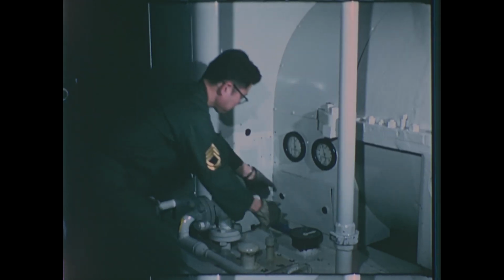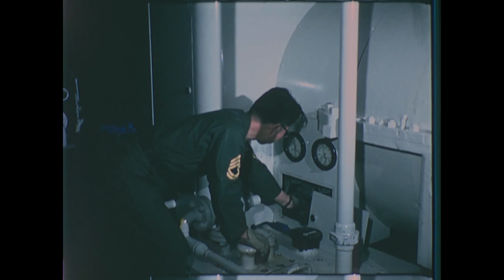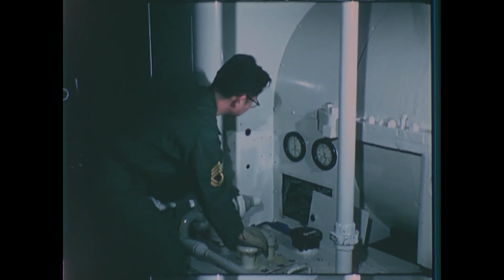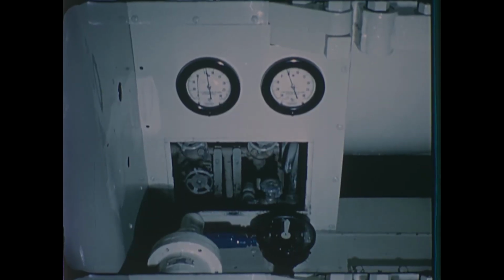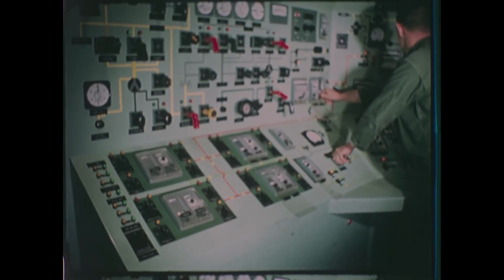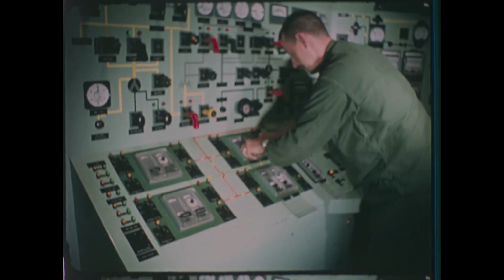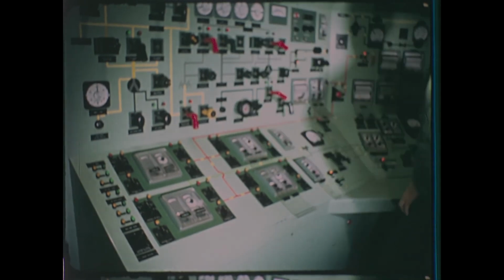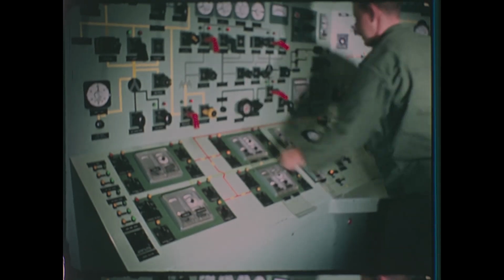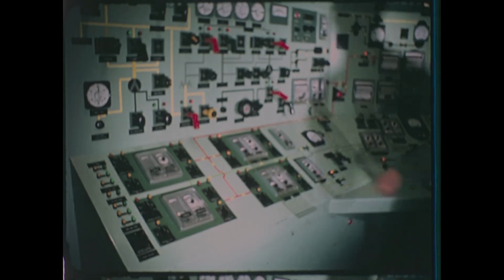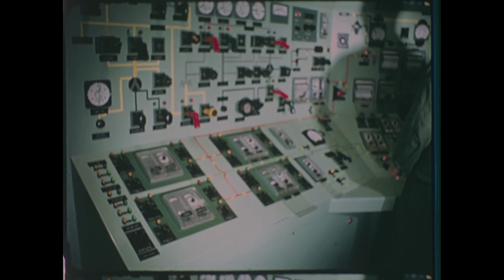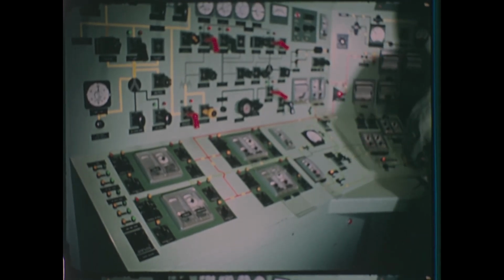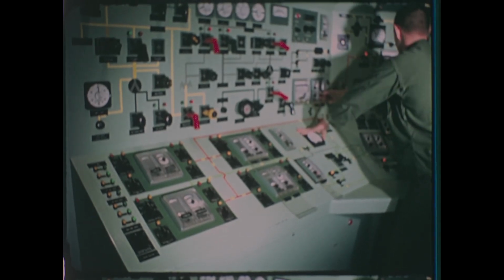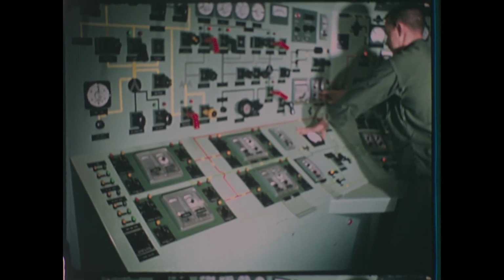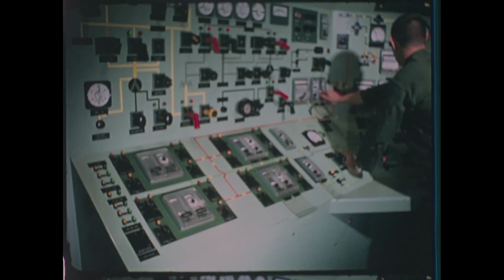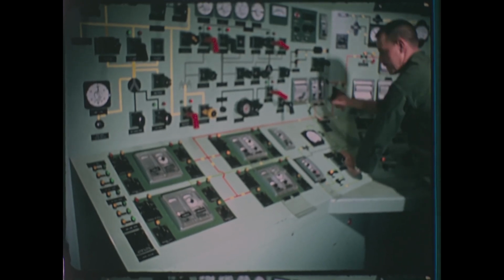He adjusts the gland seal steam pressure and puts the gland seal ejector in operation. Immediately, the control room operator establishes desuperheater steam flow to the condenser. He places the condenser fans in operation to maintain the vacuum. He increases the steam flow and places the second condenser in operation.